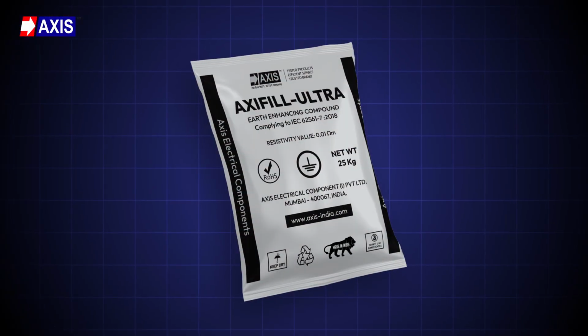Thirdly, Axifill-Ultra. Axifill-Ultra is a premium earth enhancing compound made from graphite. Unlike bentonite-based compounds, it uses multi-layer carbon structures that offer higher conductivity and longer service life. It is designed for sensitive sites where grounding needs to be stable, reliable, and corrosion resistant. What sets Axifill-Ultra apart is its neutral pH value, which is around 7.